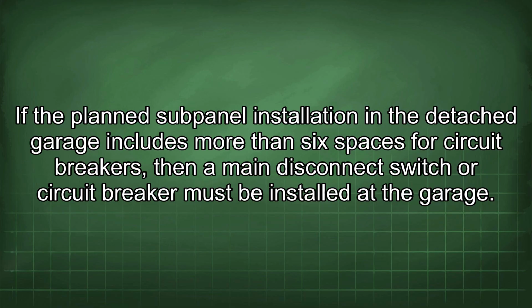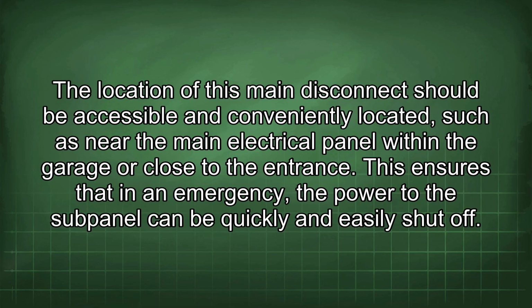If the planned subpanel installation in the detached garage includes more than 6 spaces for circuit breakers, then a main disconnect switch or circuit breaker must be installed at the garage. The location of this main disconnect should be accessible and conveniently located, such as near the main electrical panel within the garage or close to the entrance. This ensures that in an emergency the power to the subpanel can be quickly and easily shut off.